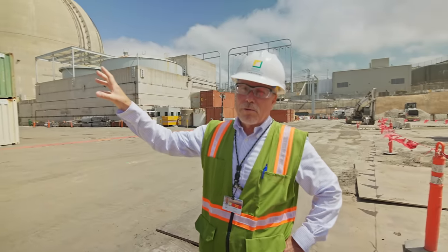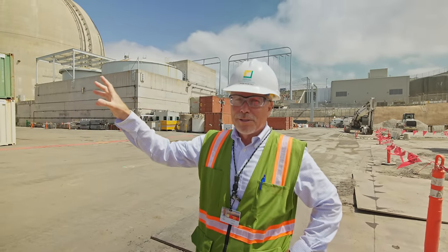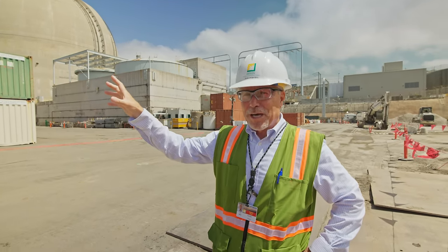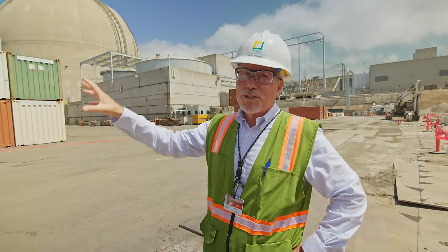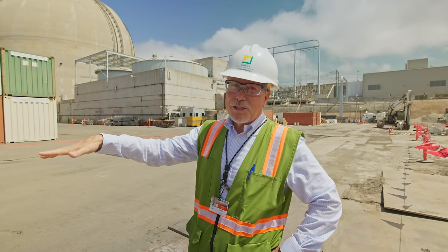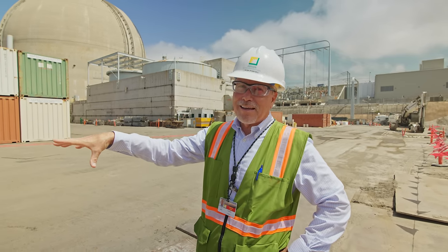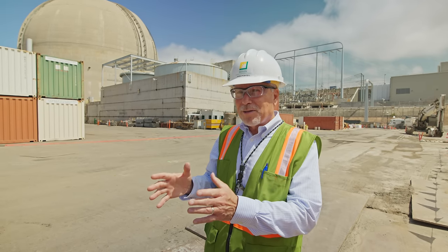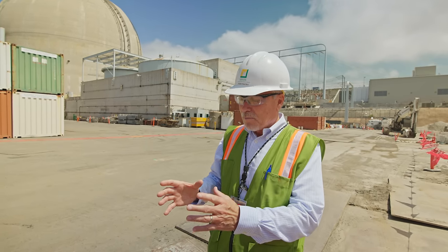The turbine generator had to be reliable in its operation, which means it can't vibrate. To prevent vibration, you need a substantial foundation. The bottom of the turbine building foundation is 15 feet thick of reinforced concrete, and on top of that foundation were built pedestals — basically columns — that rose up to support the turbine.